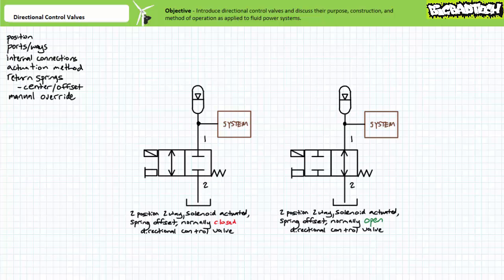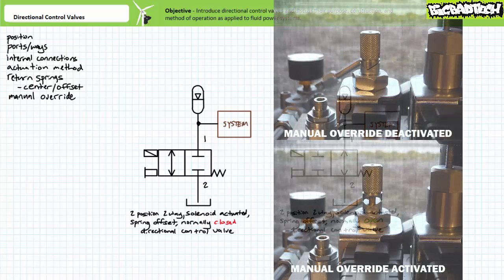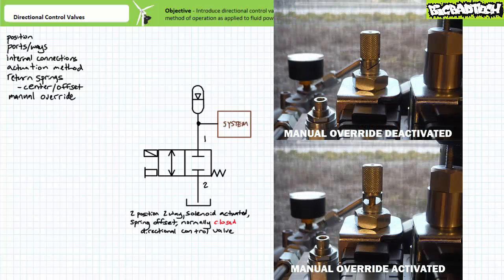Some automatically actuated directional control valves incorporate a means of manually overriding the valve's deactivated state. The schematic symbol for a manual override looks like a top outlet on its side. In the absence of a pilot electrical signal or in the event of a damaged solenoid coil, an operator can push or pull the manual override to actuate the valve. The manual override on the normally closed valve would dump the pressurized fluid in the accumulator to tank. Manual overrides may or may not feature a detent that locks the valve in the new position.